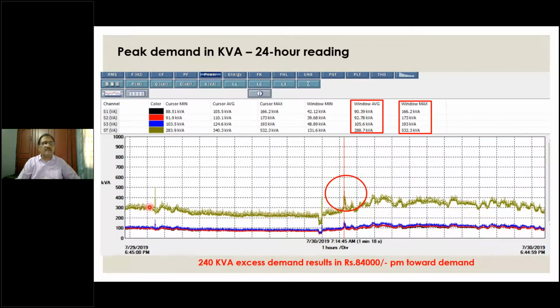So this graph will help you to understand. So this is in the morning, when as soon as they come, they must have started some activities. So 500 kVA is registered in the meter as the peak kVA. And in the afternoon, when the chiller loads are started, this is a children's hospital. So children in the morning hours will be generally comfortable. Afternoon, after the sun becomes hot, they will be starting the chiller, and therefore this must have happened.